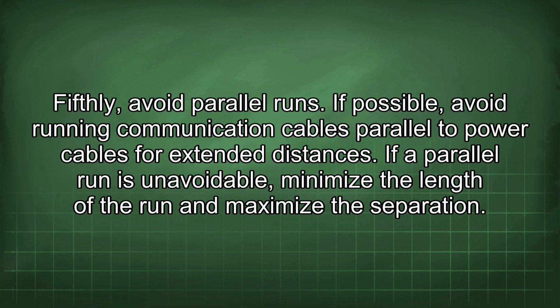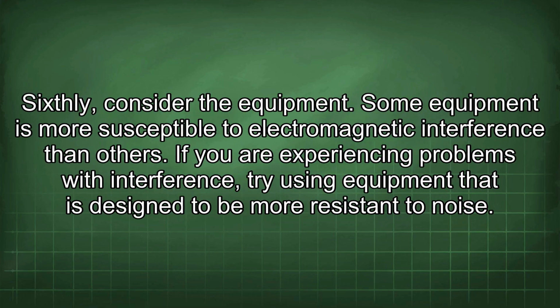Fifthly, avoid parallel runs. If possible, avoid running communication cables parallel to power cables for extended distances. If a parallel run is unavoidable, minimize the length of the run and maximize the separation. Sixthly, consider the equipment.